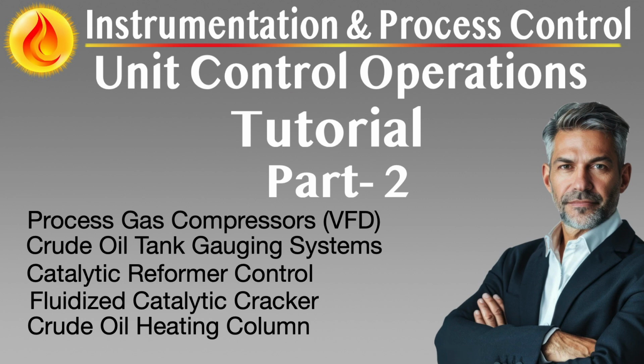Energy efficiency is a major focus area in reformer control. Furnace duty, feed preheat, and heat integration via economizers or waste heat boilers must be optimized to minimize energy intensity. Infrared sensors and oxygen trim control systems are used to maximize heater efficiency and detect early signs of burner imbalance or tube fouling. Control systems monitor fuel-to-air ratios and can automatically adjust burner profiles based on load conditions or heat balance targets.